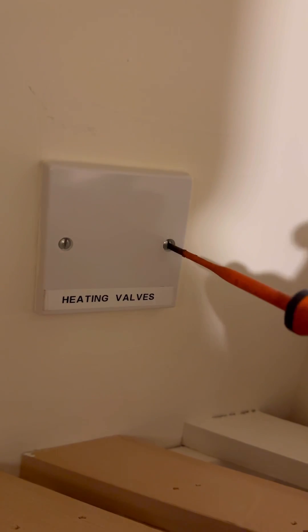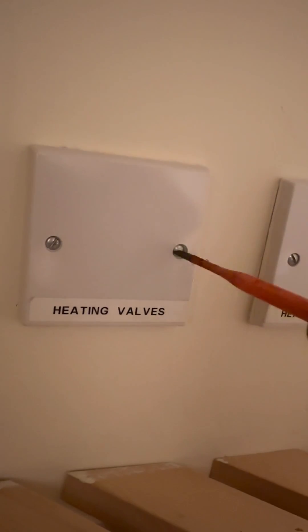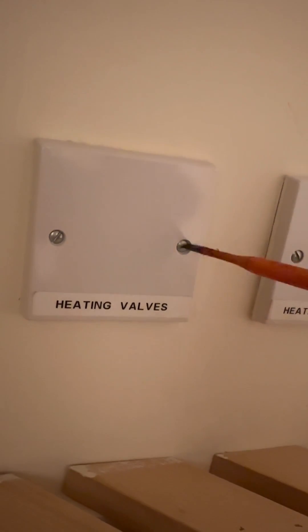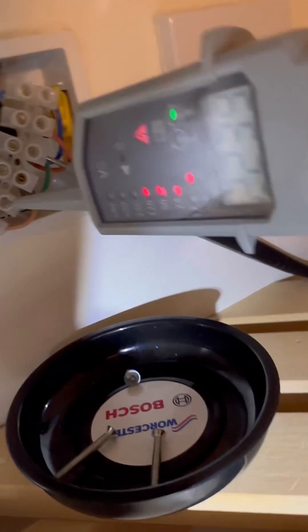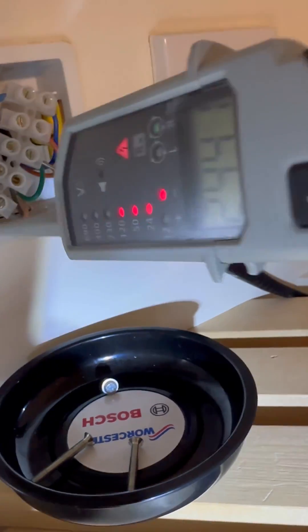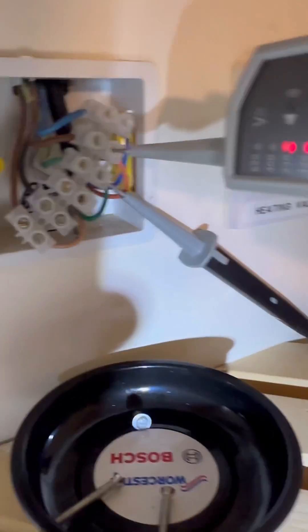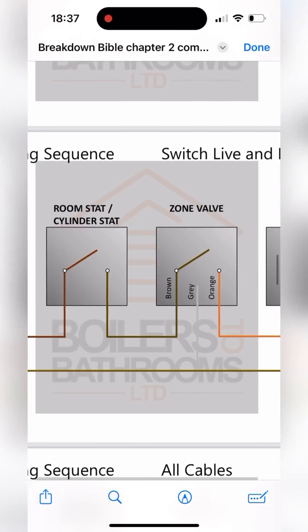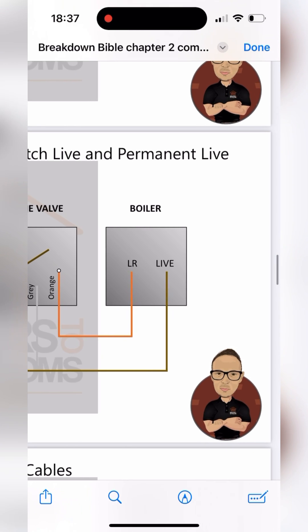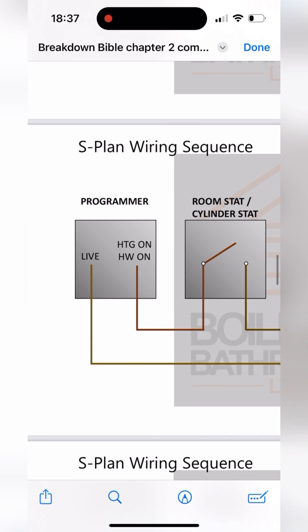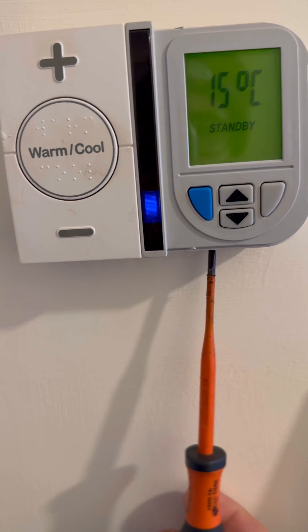Let's get that wiring center open. Grey is our permanent live, so we're going to check we've got permanent live there - we do. We're getting 240 on brown which is coming from the stats, 240 on orange which is what's firing the boiler. The orange goes from the zone valve to the boiler but it comes from brown, which comes from the room stat or cylinder stat.